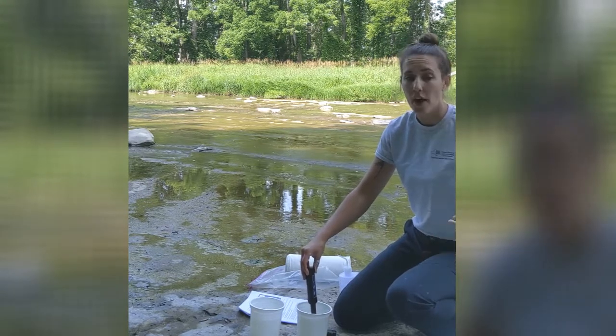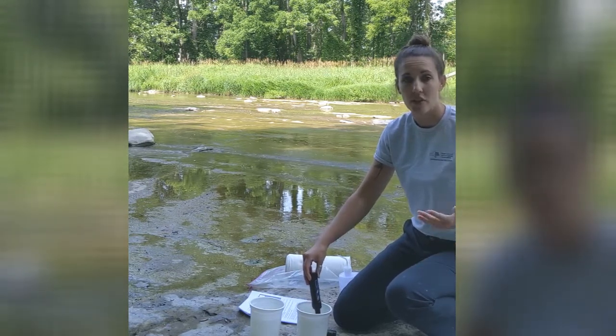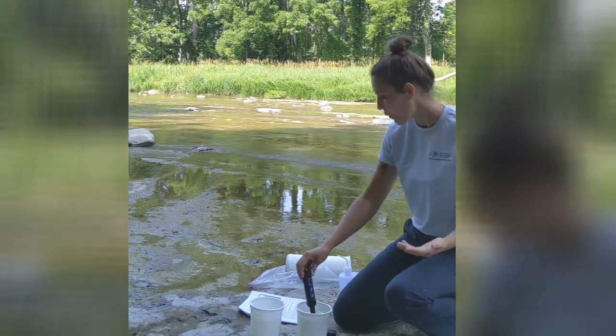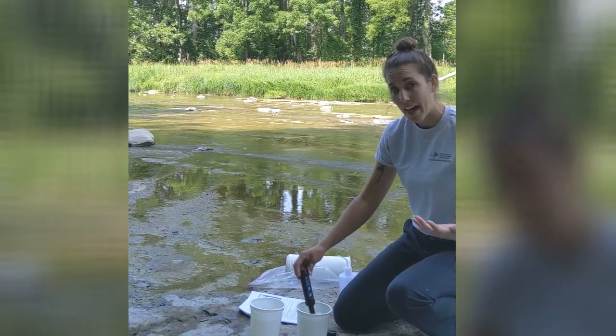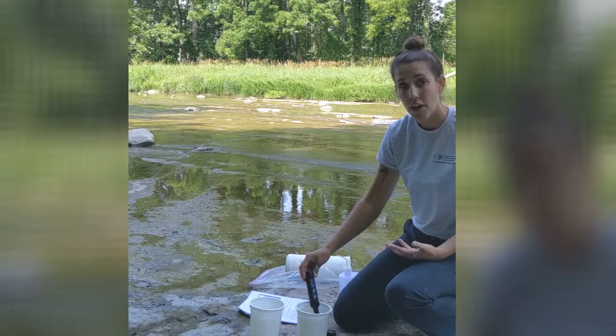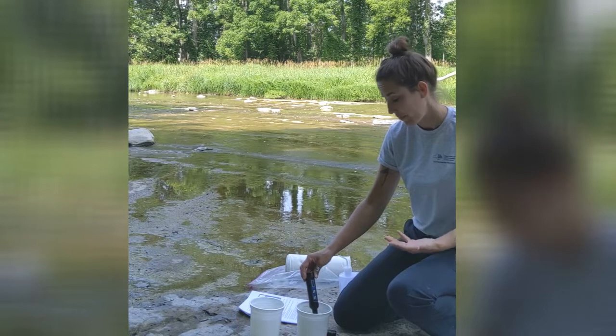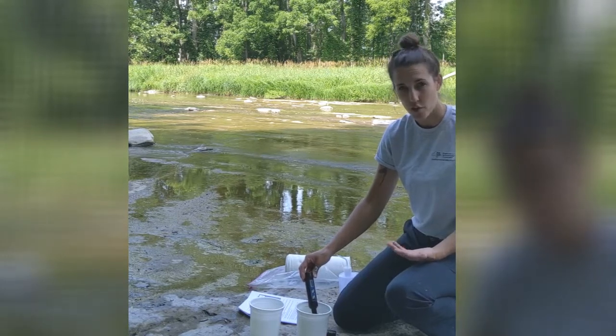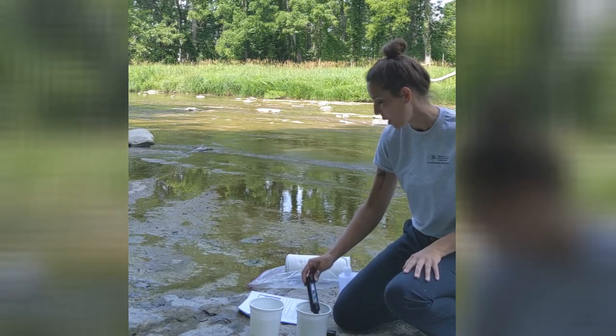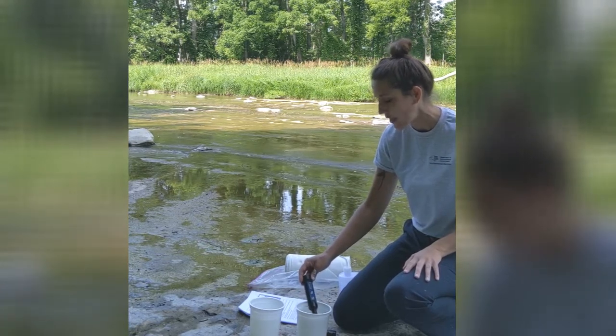You're going to leave it submerged for at least 1 minute. Now if you don't have a timer of any sort on you, you can just sing happy birthday slowly 2 times. Now, after that minute has passed, you're going to take a look at the numbers on your probe. If they are still moving, you're going to wait an additional minute. Once those numbers stabilize or stop moving, or if they're just kind of fluctuating between the two, that's okay. Then you're going to record that number on your data sheet.